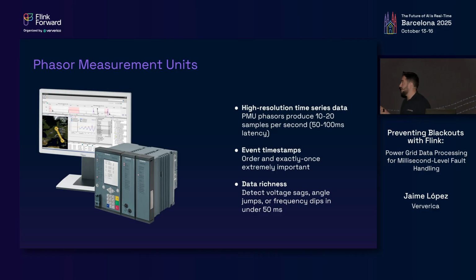You also get event timestamps from PMUs, which now starts to bring us into the event-driven programming and Flink world. You have to manage the order of those events. Obviously, in a time series, the order matters, and you also need to be able to guarantee that you process each event once and only once. If you do this well, you can actually add a whole layer of robustness and protection to the grid just by virtue of having better data.